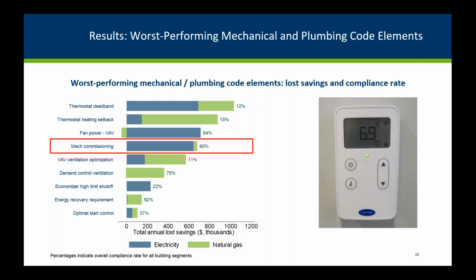Mechanical commissioning is critical in ensuring that the system is operating at optimal conditions and with the proper control sequences. Commissioning can have a significant impact on energy consumption in just about any size of building. We found there was often a lack of a commissioning plan, which suggests that commissioning was not planned for in the design and not carried out in the field.